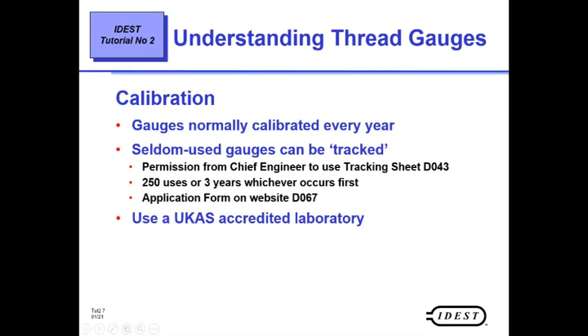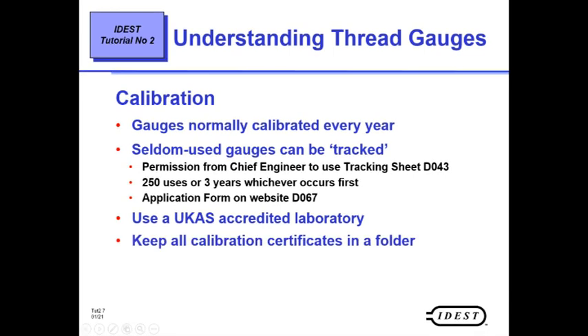Always use a UKAS accredited laboratory to have your gauges calibrated. The reasons are given in tutorial number 1, and make sure that you keep all your calibration certificates in a folder, because this will help you track how your gauges are wearing over a period of time. Finally, look at IDEST tutorial number 1 for more details on calibration certificates and the information contained within them.